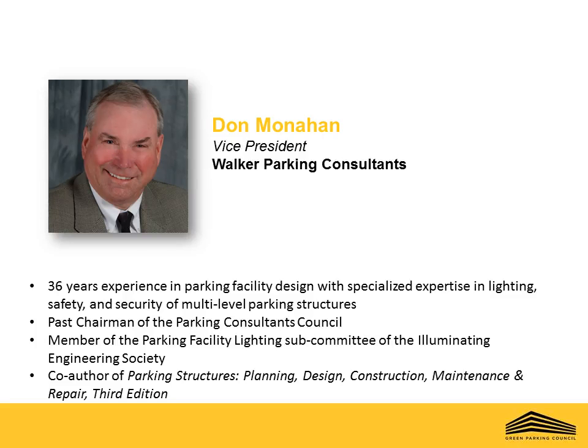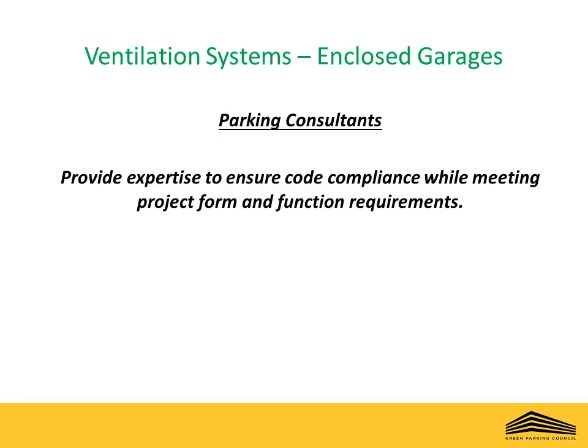Thank you, Trevor. As parking consultants, the building code requires us to comply with mechanical ventilation of enclosed parking garages, which requires knowledge of how to best implement those systems. Older building codes required that the exhaust fans run continuously regardless of the level of vehicle emissions, which obviously uses excess energy. Changes implemented in the 2003 International Mechanical Code allowed automatic detection of vehicle emissions to activate fans if excessive levels of harmful vehicle emissions were detected. This approach was much more energy efficient.